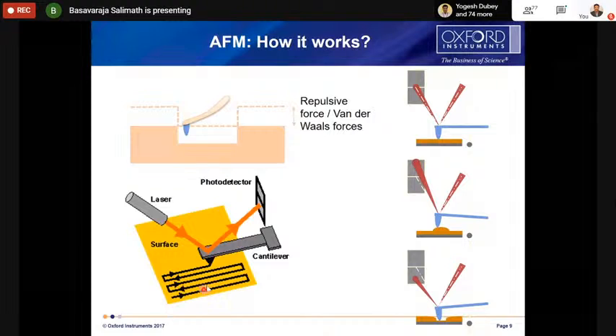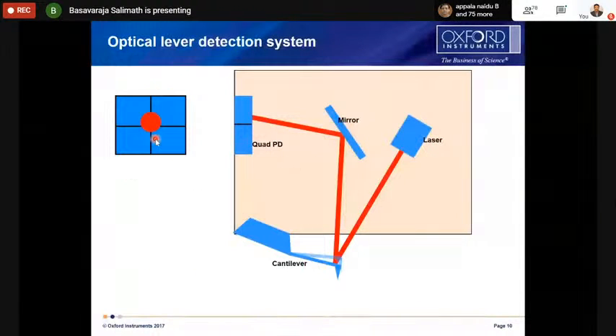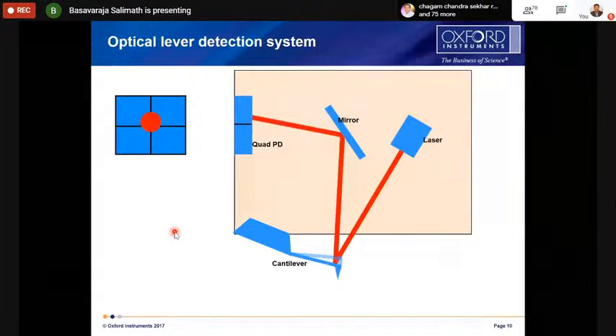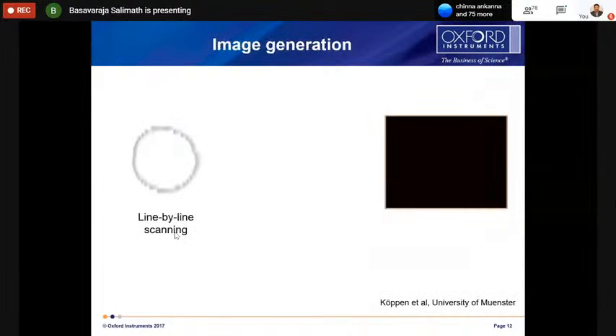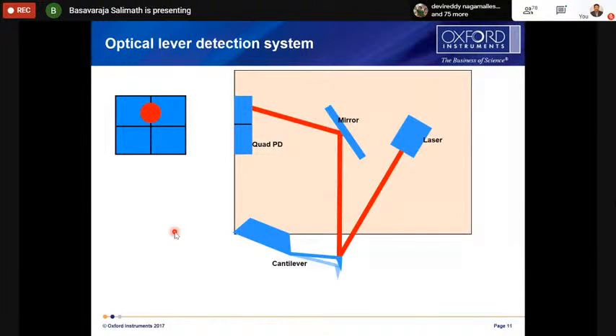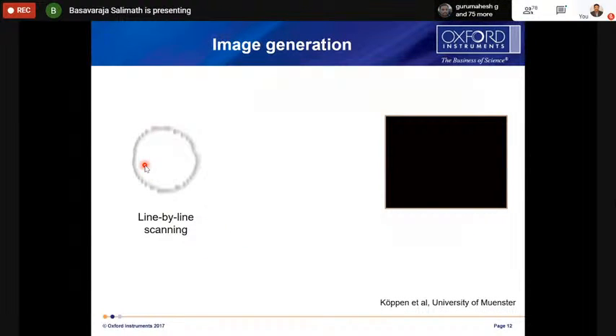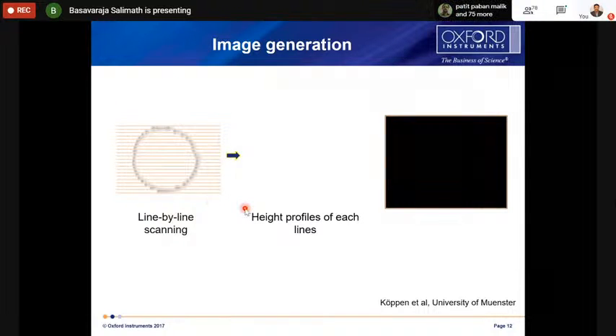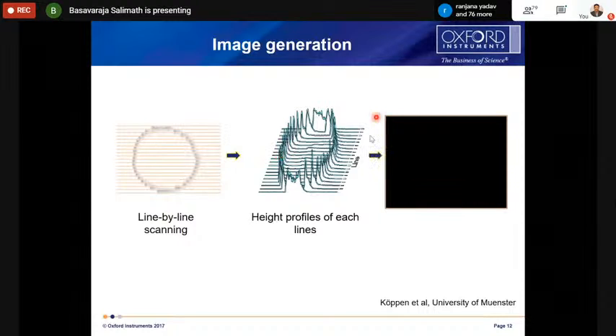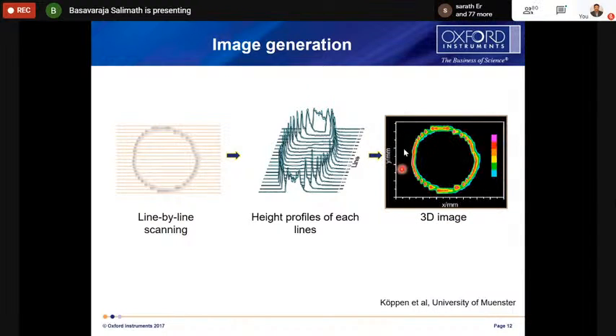So this photodetector is telling us how the tip is actually moving while scanning laterally. As I also told you earlier, the AFM is doing line by line scanning. Initially it will be at the center, and you can see the difference as it goes up and down. Now assume that there is some spherical feature in your sample. AFM is doing line by line scanning on that, so for each line we get an X versus Z profile, showing how the tip is moving. If you combine all these line height profiles, you get a 3D image. That is how it generates a 3D image in the AFM.